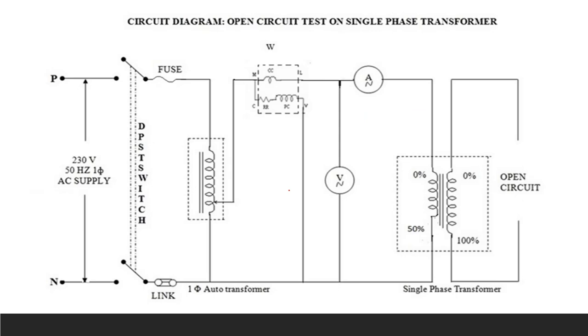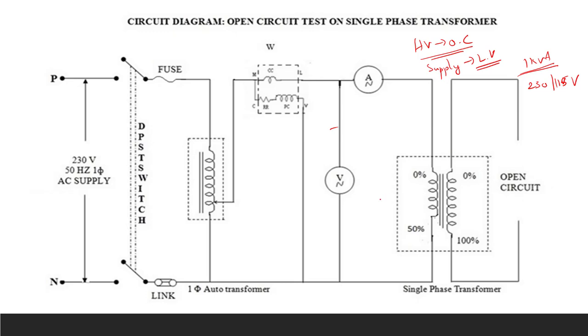This is the circuit diagram for the open circuit test on a single-phase transformer. Normally, the open circuit test will be conducted when the high voltage side is open circuit and supply will be given to the low voltage side. We have connected a 0 to 50 percent range. For example, we have a 1 kVA transformer — a 230/115 volt transformer in our lab. We are going to connect 0 to 115 volt on the supply side and 0 to 230 volt on the secondary side.